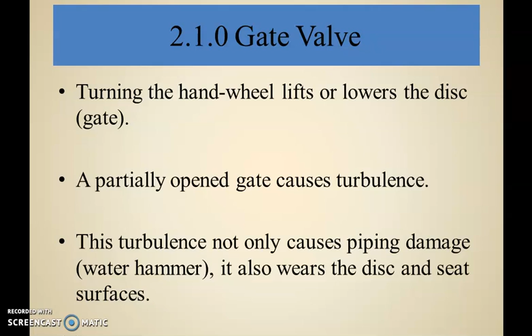Partially open gates cause turbulence. This turbulence not only causes piping damage, there is water hammer, and we also call it cavitation. It also wears the disc and seat surfaces. It may bend the disc or seat surface, due to which, if you use this gate valve for controlling purposes, that valve will start leaking after some days because of the wearing of the disc and seat surfaces.